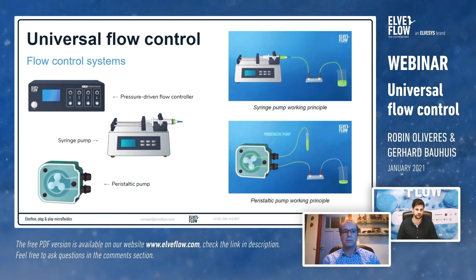A quick overview of the three main flow control methods used in microfluidics and low flow: syringe pumps, peristaltic pumps, and pressure-driven flow control. In a syringe pump, liquid is pushed by the mechanical movement of a plunger, offering good volumetric control, but the non-linearity of the mechanical movement leads to a quite pulsatile flow and long response times in the several-second range. Peristaltic pumps use the rotary action on flexible tubing, but lead to an even more pulsatile flow.